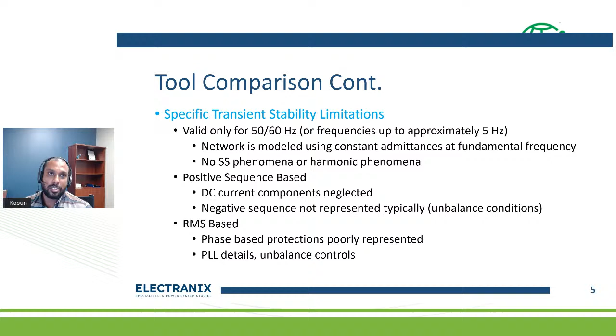One of the main limitations in transient stability, RMS based tools is the large simulation time step. PLLs and the inner loops of control systems, especially new renewable power electronic based controllers, have very fast time constants that need small time steps to simulate. RMS based tools use large time steps instead, so we lose this information and accurate modeling, and usually have to simplify the control loops to operate with larger simulation time steps, along with convergence issues.